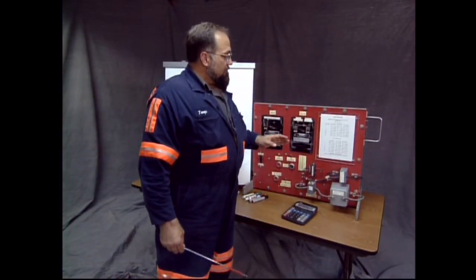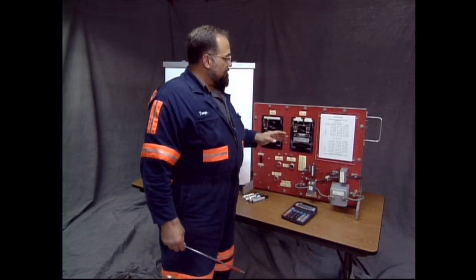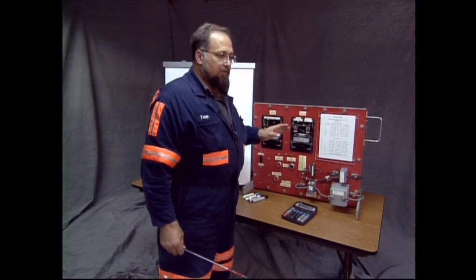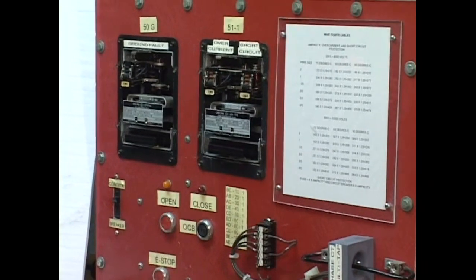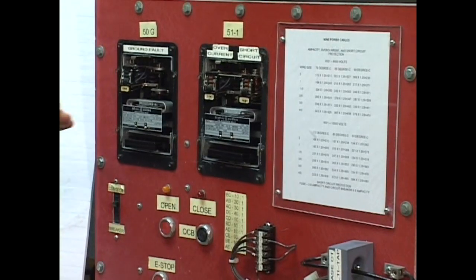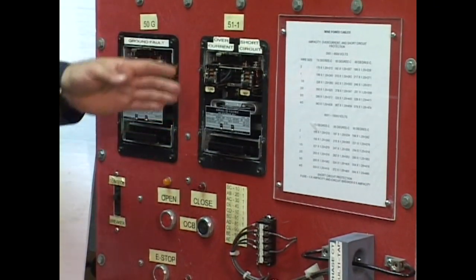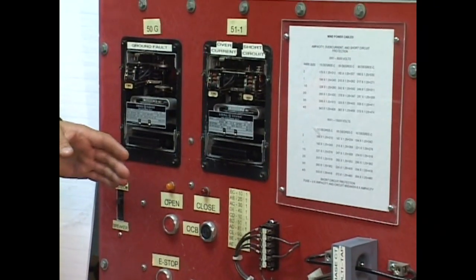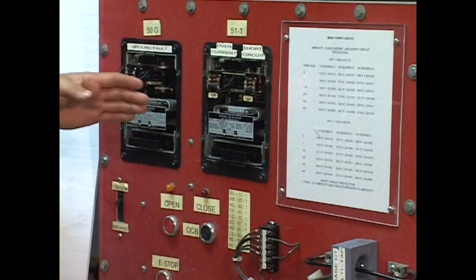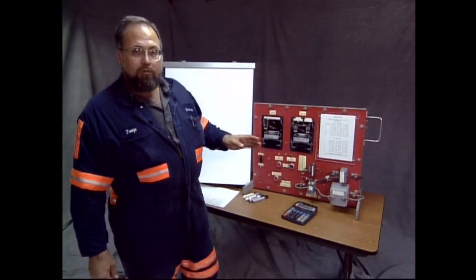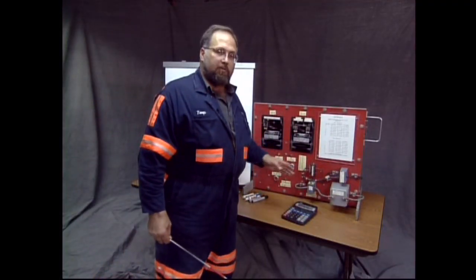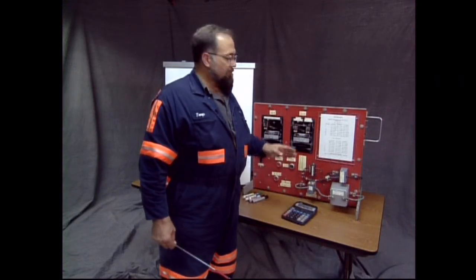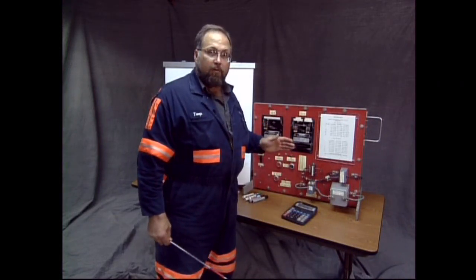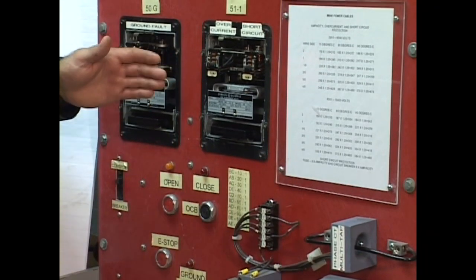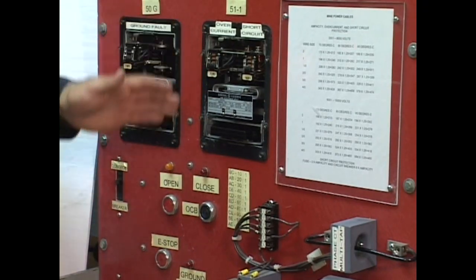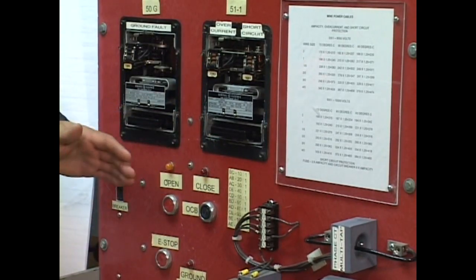Here's how. Now this relay is virtually infinitely variable. It's got numerous taps. And you use the overcurrent tap, which is located in the rear. I'll be pulling this out and showing you in a bit, as a multiplier times the CT ratio. And that says when this thing will trip. The current value is a product of the multiplication of the tap times the CT ratio. At that current, it will trip.